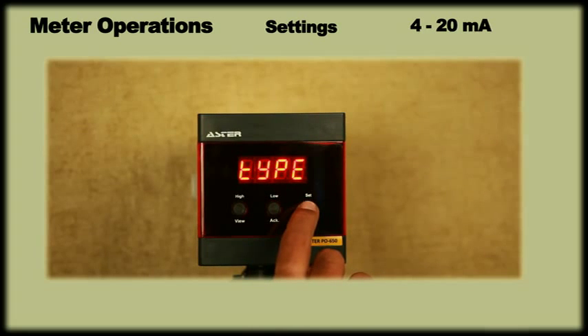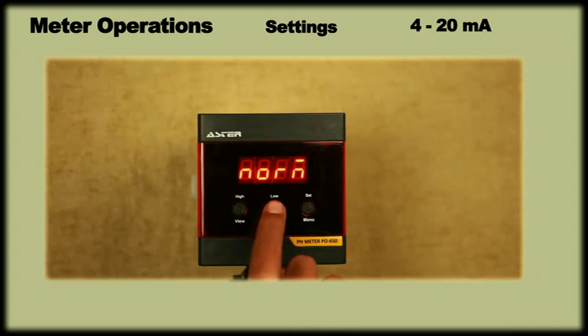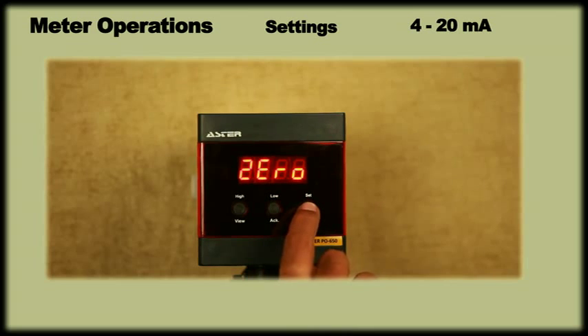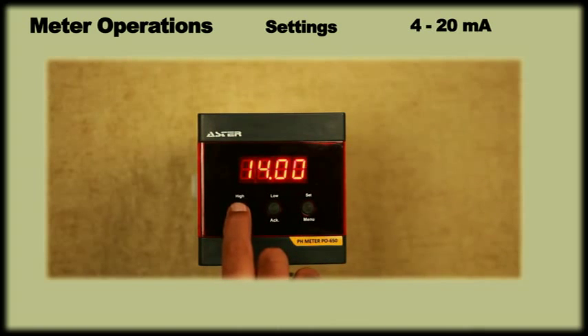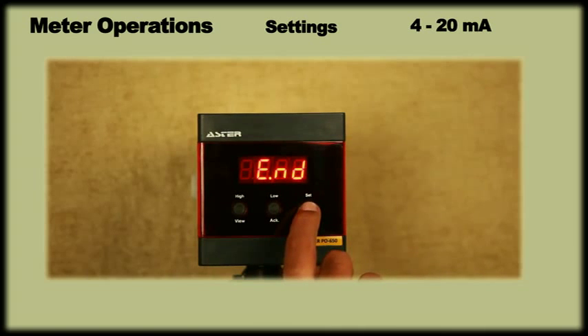On pressing menu, display will show type. On pressing menu again, we can choose the type as either normal, that is 4 to 20, or inverse, that is 20 to 4, using the ACK key. Then press menu to save and set the 0 value. After setting the 0 value, press menu twice to set the span value. Having changed the span value, press menu twice to end and save the setting.